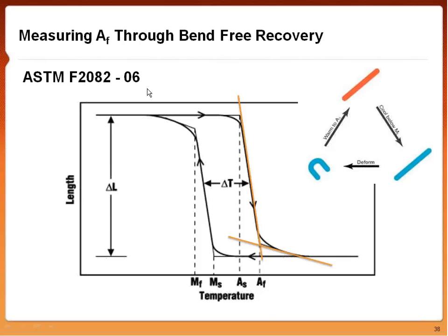Now, the ASTM standard says that for wire, you need about 2% strain in the material. What we care about most is how functional your device is going to be. So when you take a stent, the point of it is you crush it, cool it down, put the weight on it, let it heat back up, and once it heats back up to its final configuration, that's what you care about: the Austenite finish temperature. You care about when the device is fully recovered to the point where it can operate.